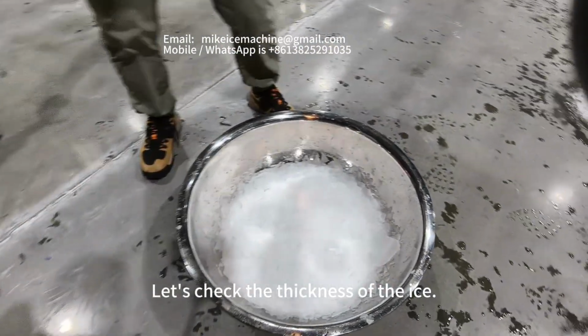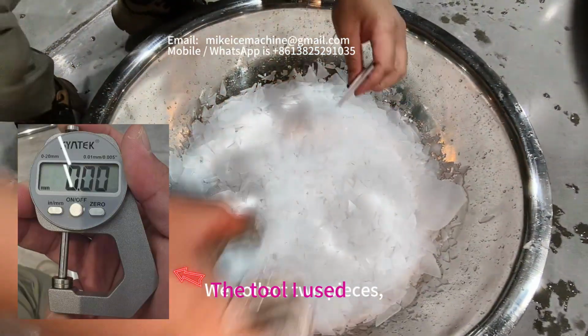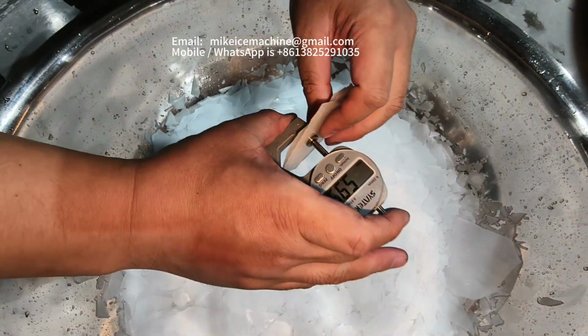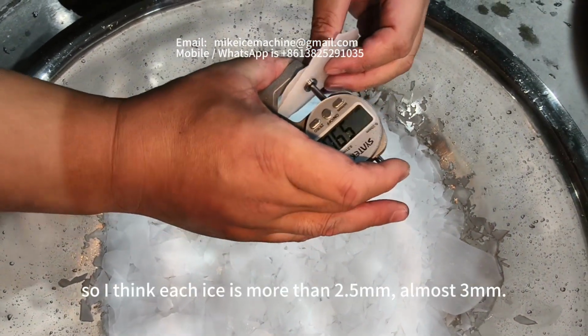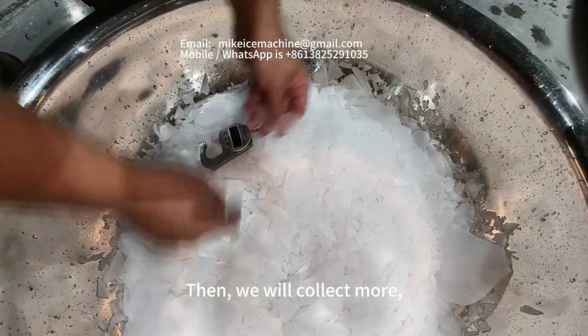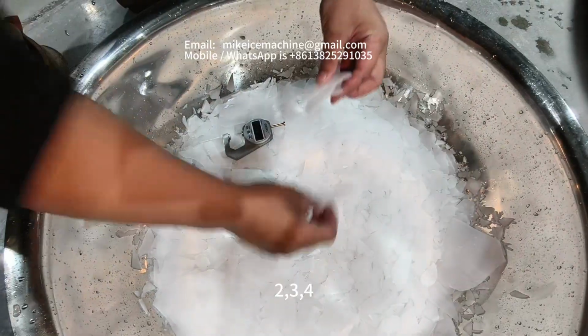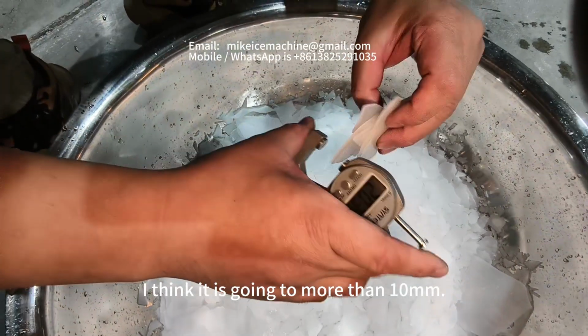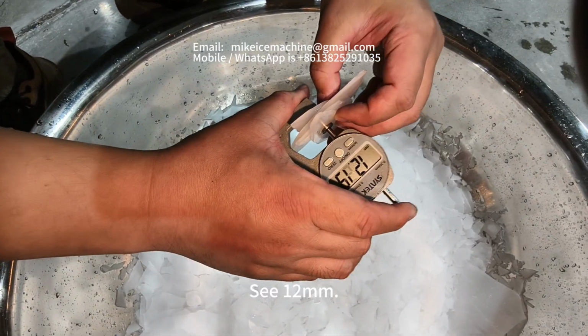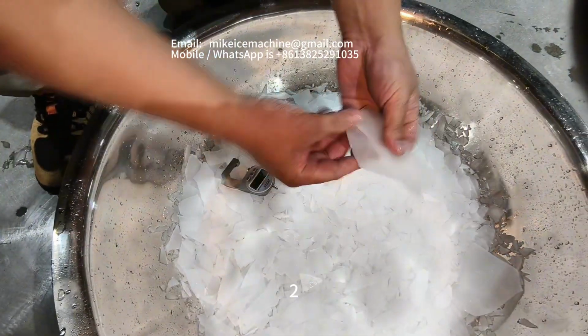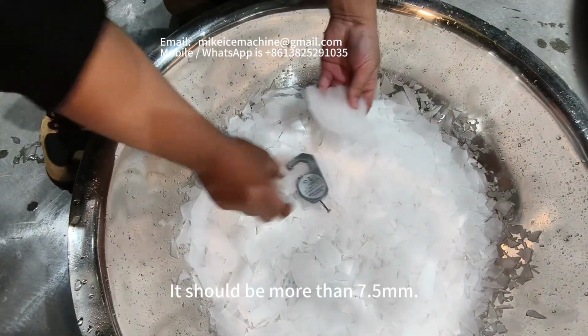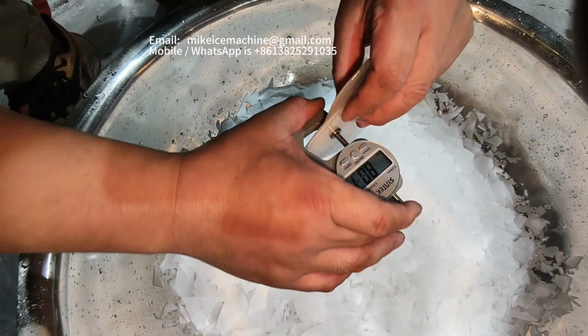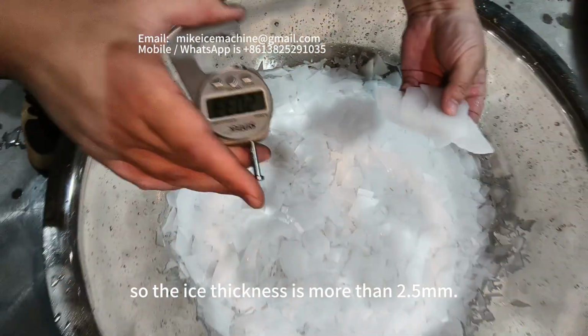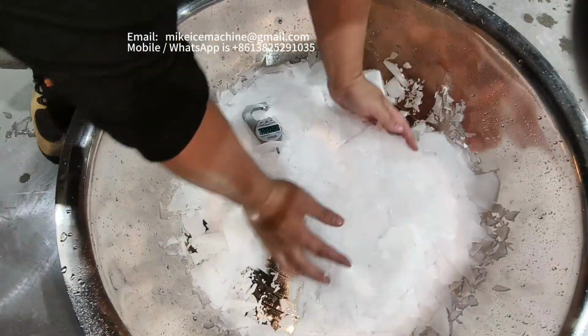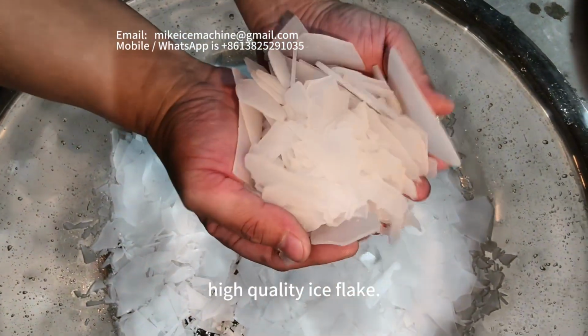Let's check the thickness of the ice. We collect two pieces, and the thickness is more than 2.5, almost 3 millimeters. Let's collect more - 2, 3, 4... I think it's going to be more than 10. See, 12, so more than 3 millimeters. It should be more than 7.5. Wow, see, so the ice thickness is more than 2.5 millimeters. This is very well frozen, high quality ice flakes.